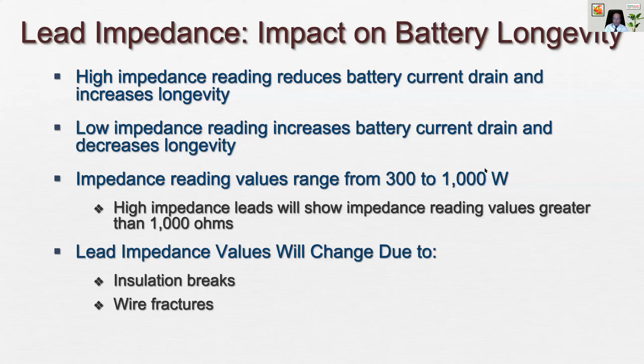And this is what I was talking about: if there is an insulation break, then the resistance will decrease and there will be more wastage. But sometimes there may be a lead wire fracture, as we can see here. That will increase the resistance. Whenever we see a rise in impedance, we should immediately suspect that the patient may be developing a fracture of the lead, and we should change the lead. So that is more dangerous.